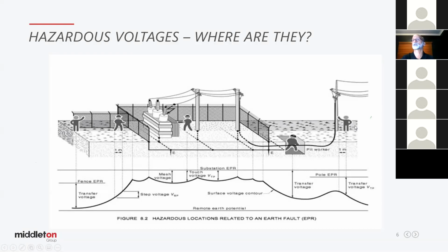Or indeed someone that's jogged along and they're leaning on a conductive pole out in the suburb, and we find that that voltage is transferred to that conductive pole. His feet are at a different voltage, so he'll experience a voltage as well. So here's where we may find these voltages: out at UGO poles or overhead-unders, depending on where you are. On maintenance workers, inside or outside of the switch yard, or just people in the public that might be leaning on a fence waiting for a bus stop. They're all potential locations for hazardous voltages.